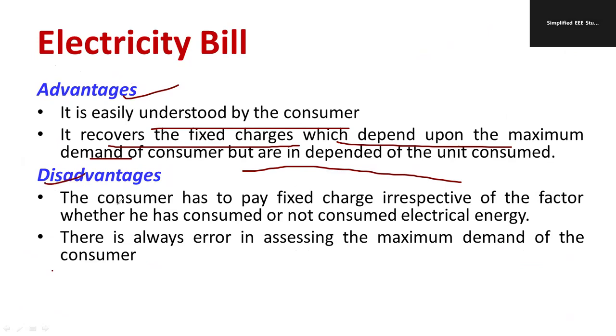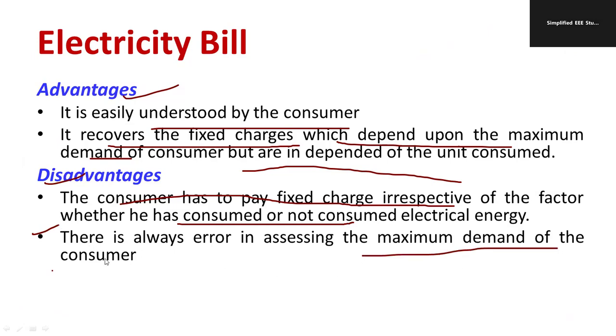The major drawbacks are: the customer has to pay the fixed charge regardless of the load power factor and consumption of load. They are least bothered whether you consumed electricity or not — you have to pay the fixed charge. That is the major shortfall. Also, there is always error in assessing the maximum demand of the consumer. Though we have a maximum demand meter, the result is not very accurate.